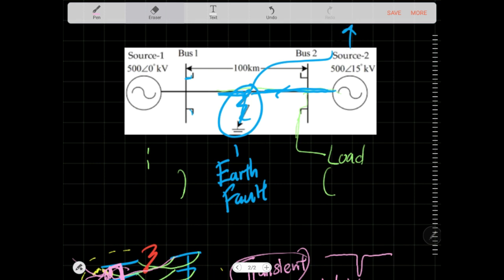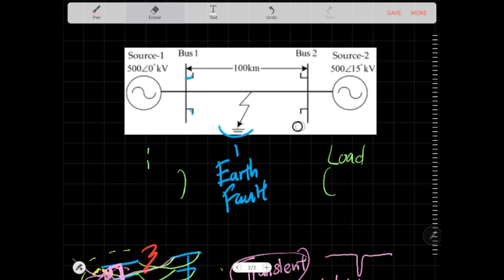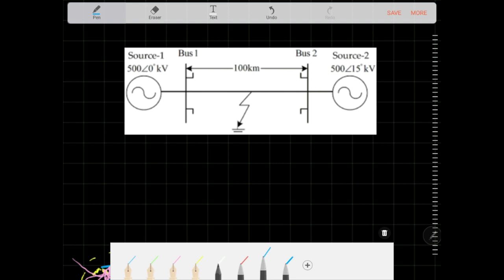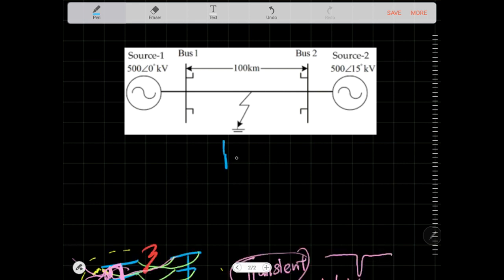If it's a permanent fault, you want to clear it. The first step is called isolation — you isolate the faulted section. Then you send your maintenance team to go and clear the fault, and after that you energize and normalize the line back, restoring supply and recovering the grid.